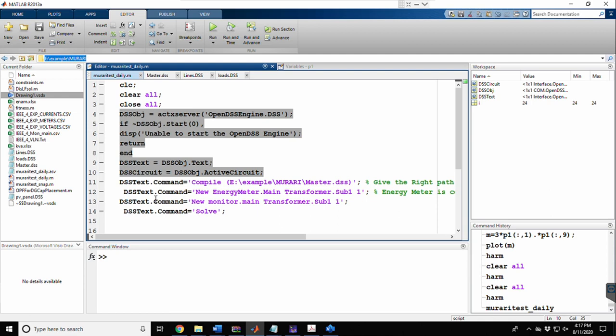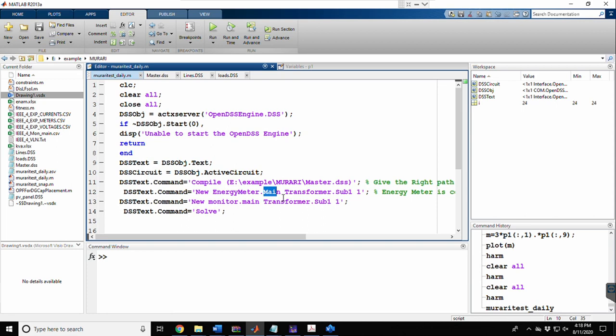In this video, I will also show some extra OpenDSS commands with additional features. The first is the energy meter, a measuring element built into OpenDSS. To insert an energy meter, we use 'new energymeter', give it a name — I named it 'main' — and place it on the transformer 'sub1'. Terminal 1 means we are placing it on the primary or high-voltage side of the transformer.